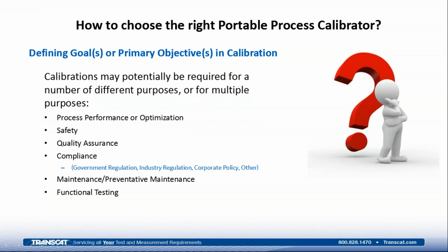Calibrations can potentially be required for a number of different purposes, or for multiple purposes. One of those could be process performance or optimization, using instrumentation to improve the quality of our products. Safety concerns are always high priorities for organizations and certainly workers within those organizations. Quality assurance, compliance, meeting possible government regulations, industry regulations, corporate policy, or other compliance-driven requirements. Maintenance or preventative maintenance. And finally, functional testing. Functional testing isn't necessarily calibration per se, but we would be using the same or similar equipment to validate functioning equipment.